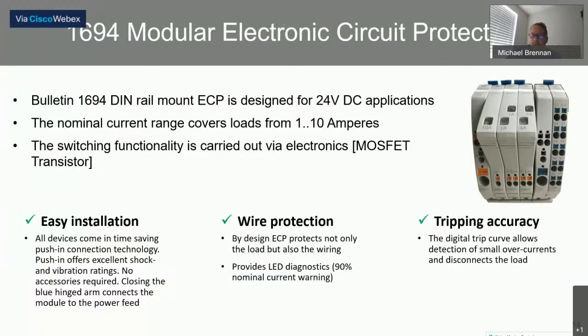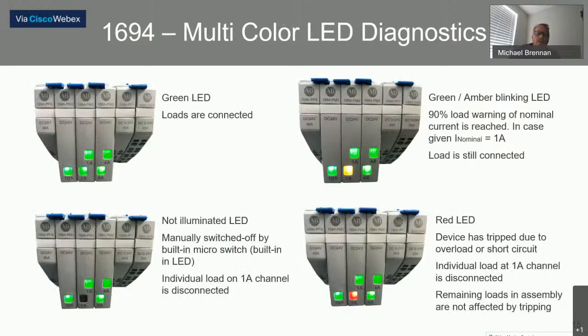And what we'll look at is there's a ton of diagnostics in these products, and there's a ton of modularity that's available. So it's easy. It allows you to add circuits quickly. It's a MOSFET design, so the accuracy of the tripping is much better than that of a miniature circuit breaker. And additionally, you can very quickly understand whether or not you're overloaded on the individual circuits as well. So here's an example of the diagnostics.